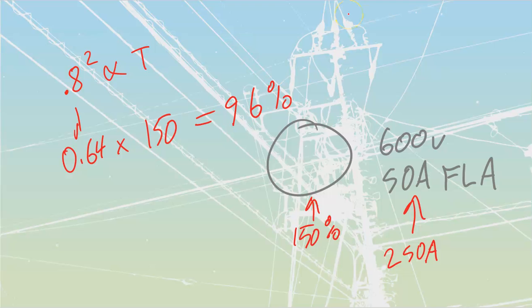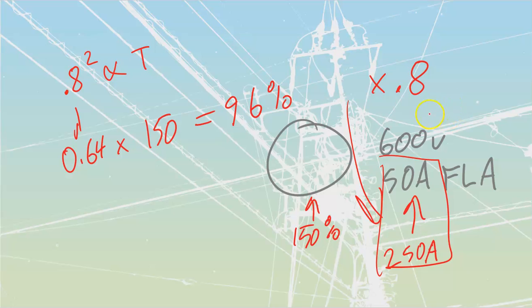It's almost 100%, but I have a very much reduced amount of voltage. We found that if we start this up across the line, we had that massive inrush of 5 times, right? But if I now reduce this, I can use that same 80% percentage. If I had 250 amps, I multiply that by 0.8, which tells me my inrush is going to be 200 amps. 250 versus 200 amps, it's not huge, but it is still significant. That's 50 amps of drop that we are reducing out of our system itself.